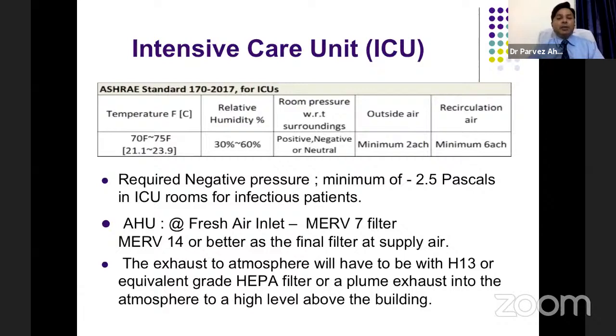Coming to the intensive care unit, ISHRAE suggests that relative humidity should be between 30 to 60%, and an ICU can be positive, negative, or neutral pressure, but especially outside air should be a minimum of 2 air changes per hour, and recirculation of air a minimum of 6 air changes. It requires a negative pressure of minimum 2.5 pascals or 0.01 inches in ICU rooms for infectious patients like coronavirus disease.